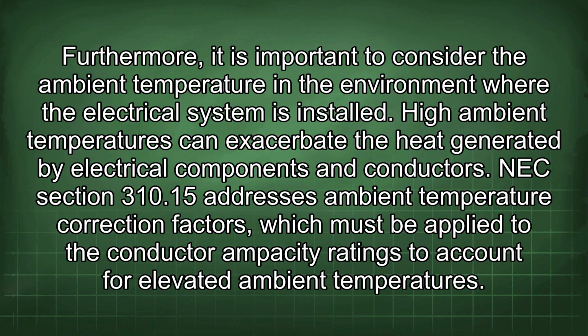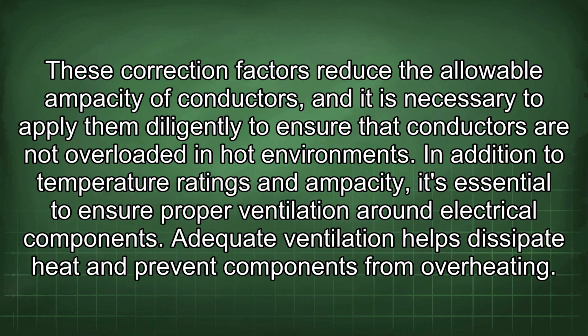Furthermore, it is important to consider the ambient temperature in the environment where the electrical system is installed. High ambient temperatures can exacerbate the heat generated by electrical components and conductors. NEC Section 310.15 addresses ambient temperature correction factors, which must be applied to the conductor ampacity ratings to account for elevated ambient temperatures. These correction factors reduce the allowable ampacity of conductors, and it is necessary to apply them diligently to ensure that conductors are not overloaded in hot environments.